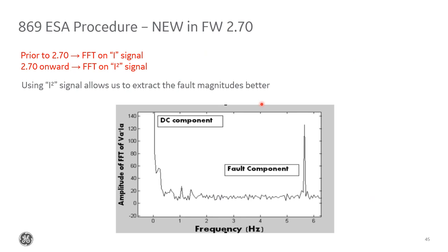So the big algorithm update I keep referencing that allows our calculations and analysis to be simplified comes into play in this step. In the older firmware versions, we simply did the normal Fourier transform like you saw in the previous slide, and we did our analysis on that. In firmware version 2.7, we still show you the normal Fourier transform signal on the metering screens because it's visually easier to understand. But in the background, what we actually do to the current signal is we take the transform of the current signal squared. So what this does is it moves the fundamental signal to DC.